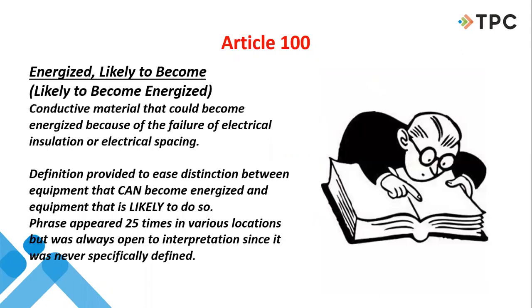Here's another one. This really plays into what we were just talking about a moment ago with the index. The term likely to become energized, the one that I have underlined, I did that on purpose. The term likely to become energized appeared more than 25 times in various locations through the previous edition. But nowhere did it ever specifically define what that actually means. Now, we all know with a term like that, when you see the word likely or words along that line, I know in the arc flash safety classes, we often have to discuss risk assessments and how risky something is.